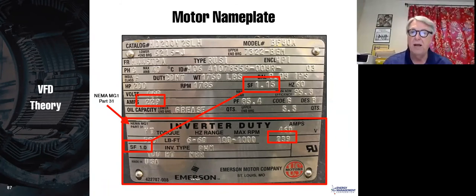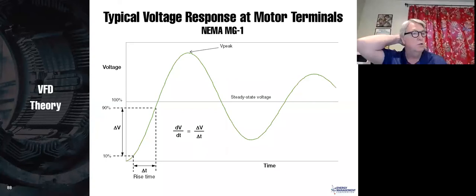This is a great nameplate. This is from US Motors. It actually has a nameplate for across the line and for inverter duty. So that's pretty nice. Most motor nameplates do not have that. So we simply use this, but we need to know that we cannot run a service factor motor at service factor when running on a VFD because of the loss of cooling at lower speeds.